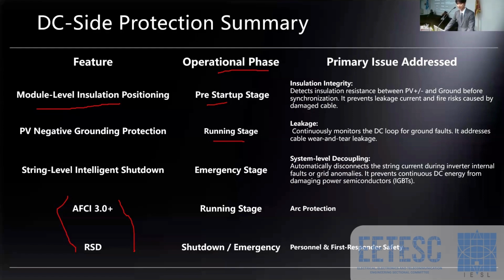And the second one is the PV negative grounding protection. In the running stage of the inverter, there is continuous monitoring of the DC loop for ground faults. So it will address cable wear and tear leakage. And the last one is string level intelligent shutdown. It is used for the emergency stage. Let me give you an example with the new release product, SG125CXP3, which we just released earlier this year.